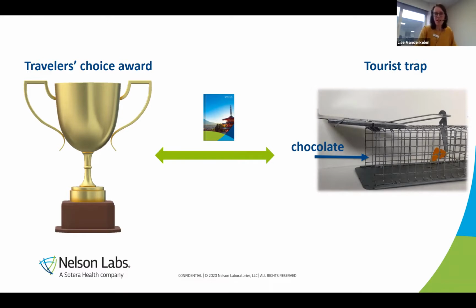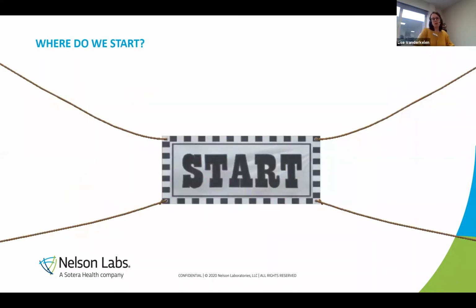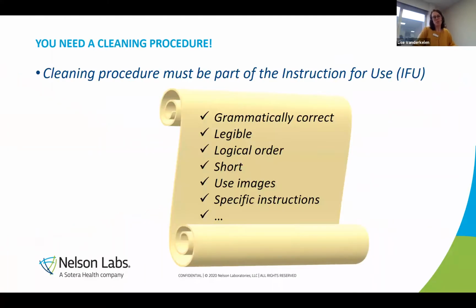So let's start. Where do we start when you want to validate your cleaning procedure? The essential document that you need to take on your road trip is a cleaning procedure. Your cleaning procedure must be part of your instructions for use. It must be, of course, very easy to read, grammatically correct, and so on, but you should use images if necessary. It should be clear instructions for the healthcare facility and the personnel that is going to clean your device, what they have to do, and how your device can be cleaned. So if you don't have a cleaning procedure, you should look for one or create one before you start this journey of the cleaning validation.